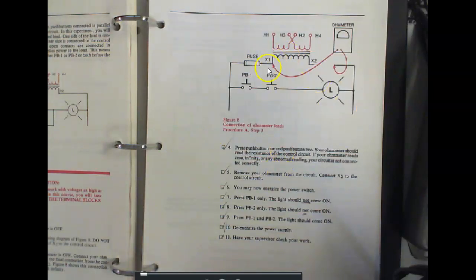So what we're doing here is we have our ohm meter. Everybody got their meter, right? Okay, and it does ohms, right? So we're going to check for a short circuit. One thing you'll find out is the resistance of a transformer is extremely low, especially on the low voltage side, because it's got more current, right?